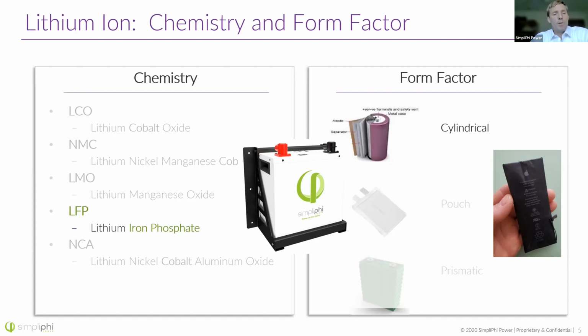So lithium iron phosphate delivers a much greater cycle life. These batteries are rated at 10,000 plus cycles if you're careful in the way you discharge them. If you're charging and discharging, cycling your battery once a day, that's 27.4 years. So you can get a lot of lifetime out of lithium iron phosphate. It's really one of the best chemistries, if not the best, for cycle life.